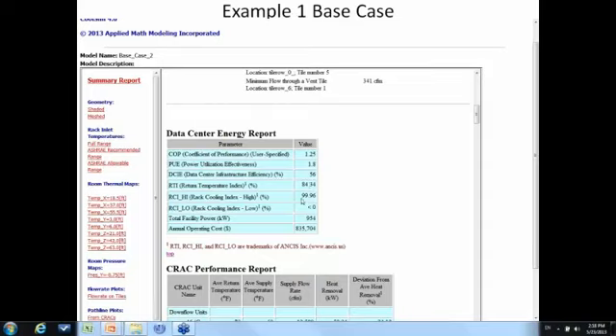Now, the RCI high is 99%, which is telling us there aren't many hot spots in this room at all right now with all those CRAC units running. But the RCI low is below 0. Now, what's that telling us? That we're way too cold, right? Yeah, it means that if that number is below 100%, there's too much cooling in the space, somewhere at least. Right. And in this case, it's not just lower than 100%, it's below 0, and that's very poor performance. Usually, if that number drops below 90%, it is generally considered to be poor.